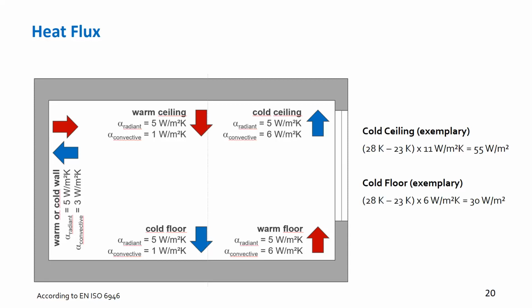And it could be things like this, and I already allowed myself to say, if the surface temperature is 23 and if the room temperature is 28, then we can expect a heat flux from the ceiling of 55 watt per square meter, and we can expect a heat flux from the floor of 30 watt per square meter. And that's enough for a decently built building. If you need more, I think we should redesign our building, at least in areas I live.